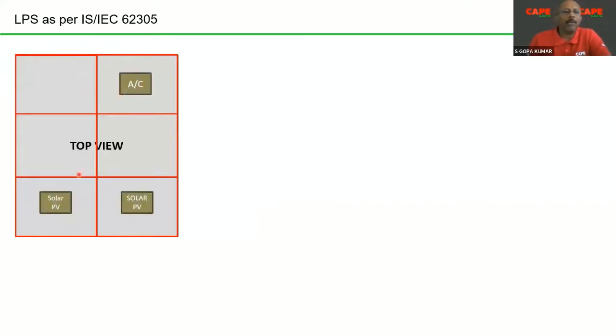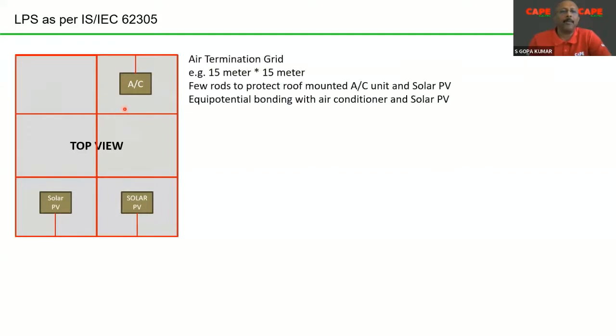Let's say, for example, I have made a mesh and there are some electrical items, like a solar PV, an air conditioner, a chiller, which are above my mesh. In that case, I have the option of making equipotential bonding, and probably the option of making some rods near the solar PV, maybe 2 rods near the solar PV and 2 rods near the chiller, so that these rods avoid the direct lightning strike into the chiller. This is a typical case.